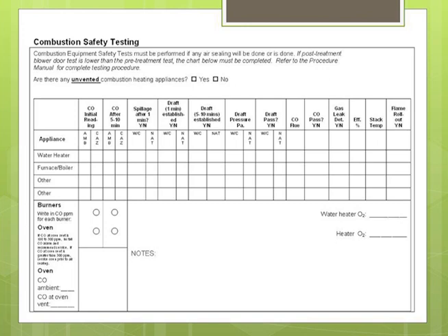If it failed the spillage test, we would actually measure the pressure inside the flue compared to the Combustion Appliance Zone to see if there were any problems that could lead to flame rollout or flue gas spillage. We'd see what kind of draft was generated in the flue, mark that down, check for gas leaks and the temperature in the stack, and go through the whole checklist.